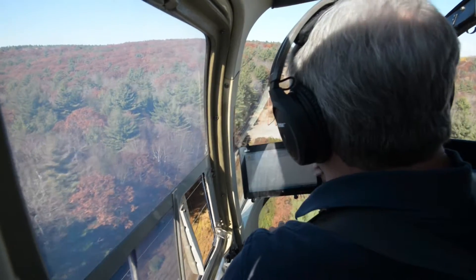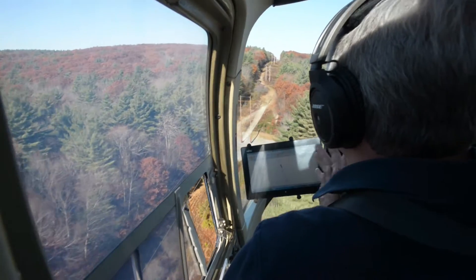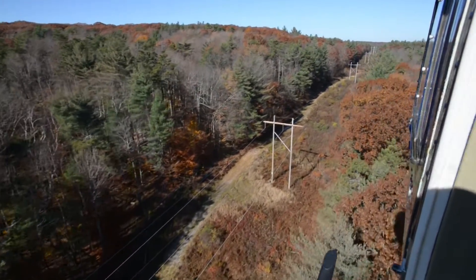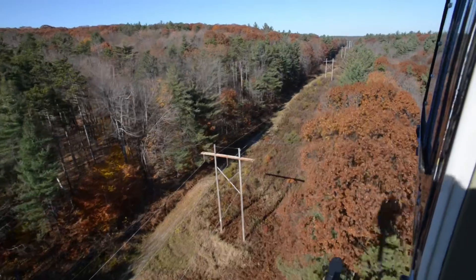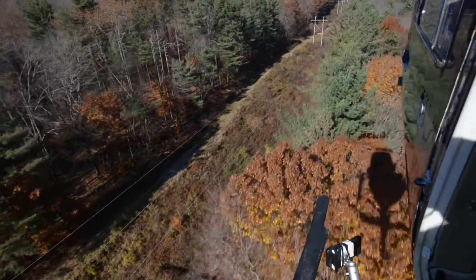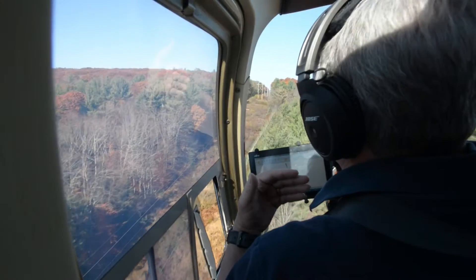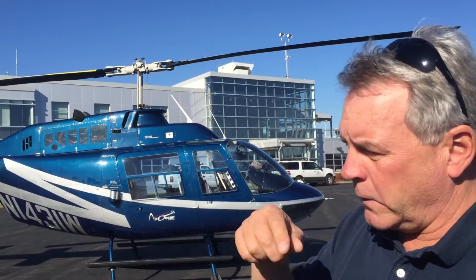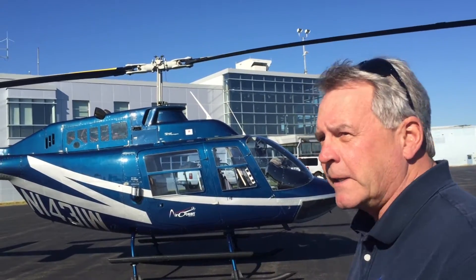We have technology now where, rather than rely on the phone lines in the street, there are relays at the substations that constantly talk to each other. We put fiber optic in and replace that shield wire with a fiber optic cable, so it's really easy to get on the skid of a helicopter, go structure to structure, unclip, pull it in, and then go structure to structure and clip it back in.